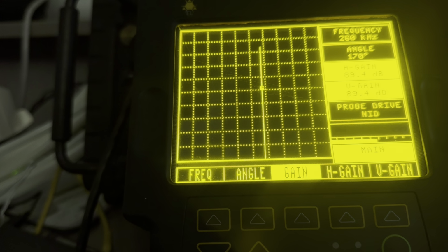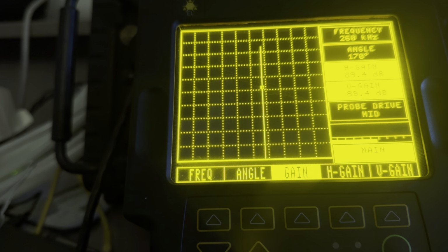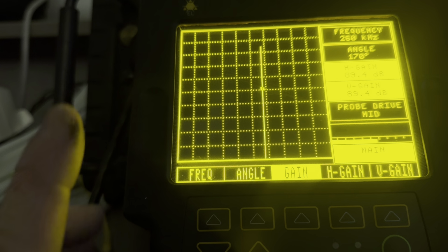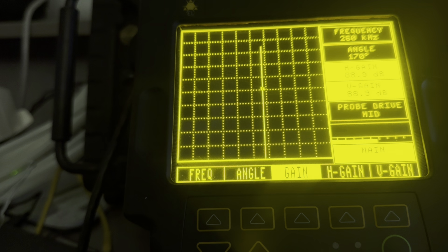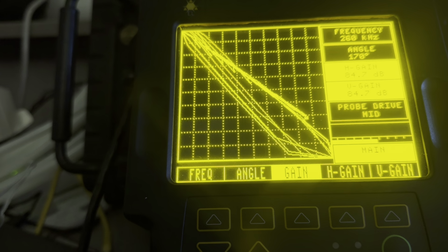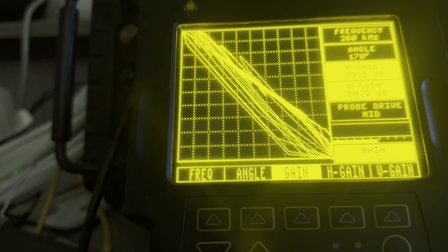Whoa, okay, so now we're getting some life. We did a little CPR on this tester and the probe, but the instrument appears to be saturated because I can't get any signals. So that shows me my gain's too high. Now, our drive voltage was set to medium. That's about 8 volts, and I know that setting works for most applications. And it's already on medium. So I've cranked the gain down a little bit. And I know the instrument. Now you can see we're starting to get some life in this probe. Take the gain down a little bit more.